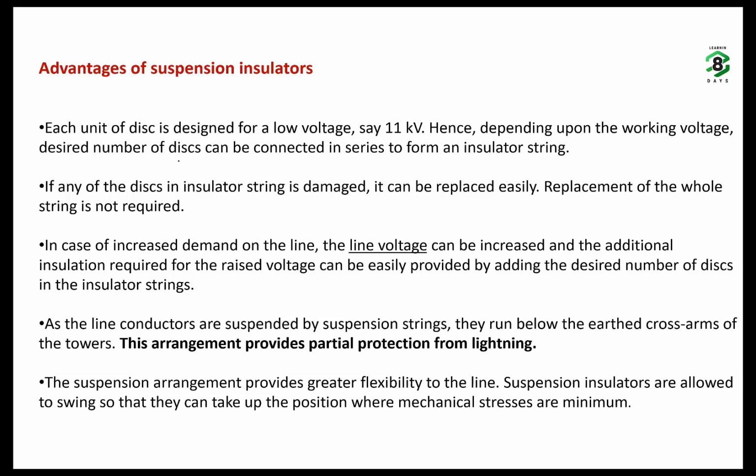Understand? By connecting the disks in series, we can increase or decrease the voltage rating of the insulator string. If any of the disks in the insulator string is damaged, it can be easily replaced. Replacement of the whole string is not required.